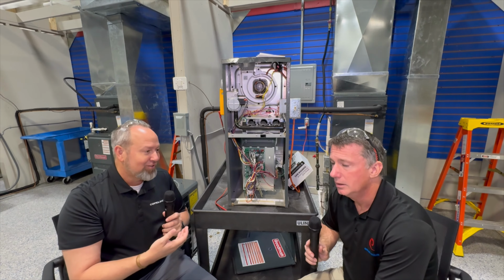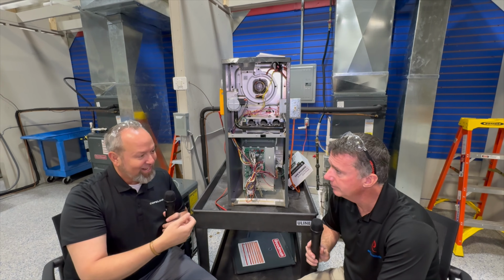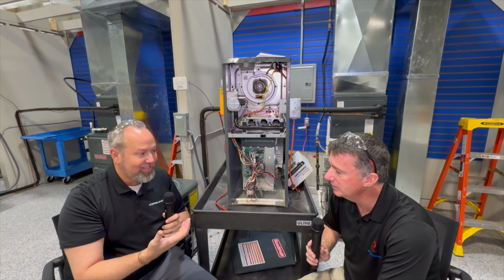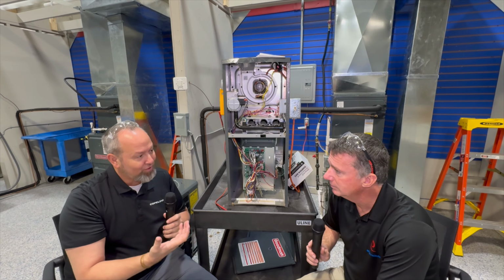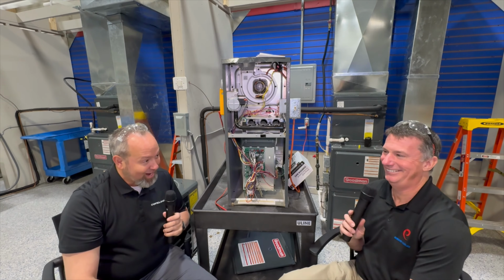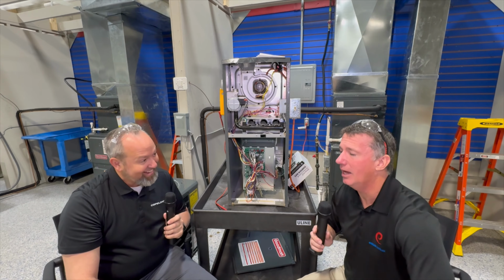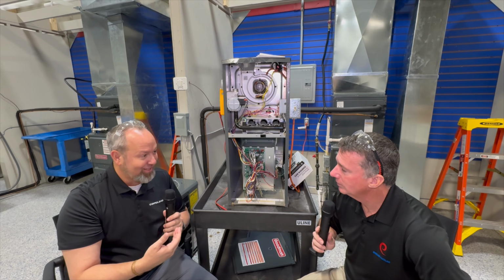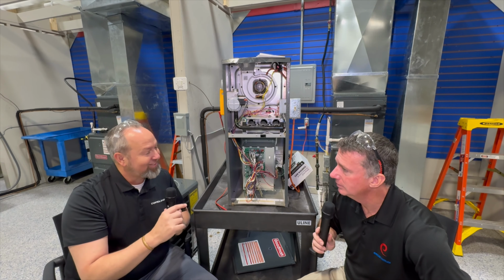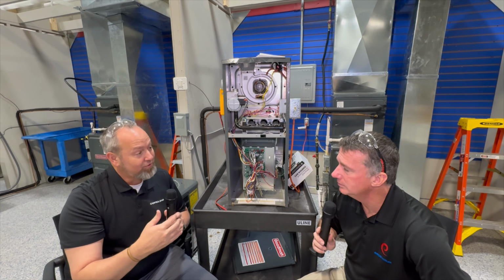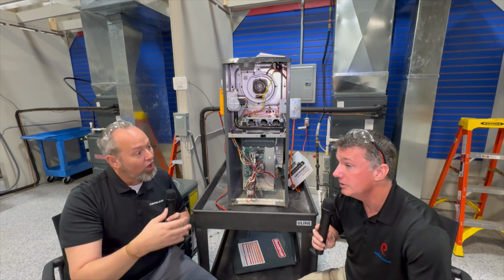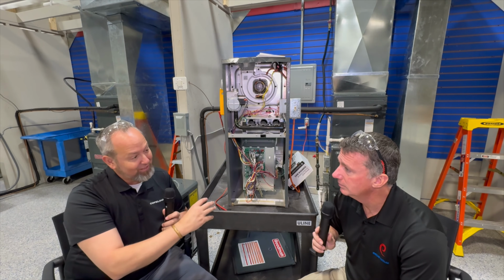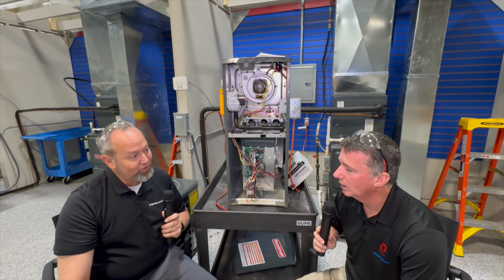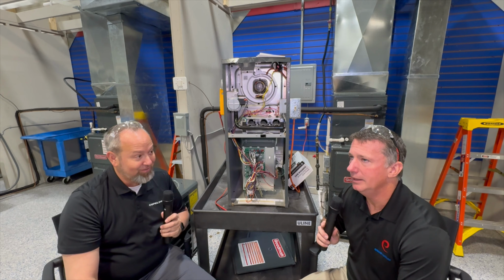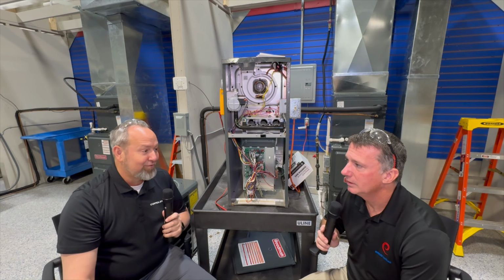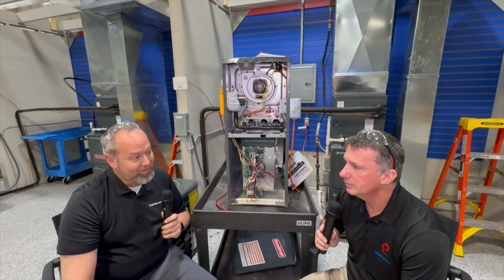With the White-Rodgers Connect, we have NFC technology, near field communication. You can actually do setup on your phone for the different fan timing settings on this, in case we need to adjust the fan timing. And in those adjustments, there is the ability to reset the harness configuration back to original OEM specification. It's actually clearing the harness that was in there, so that when you put it into something new, it starts that sequence of searching for which furnace is in again. So you do have the ability to reset that if you choose to pull it out and put it in a different piece of equipment down the road.